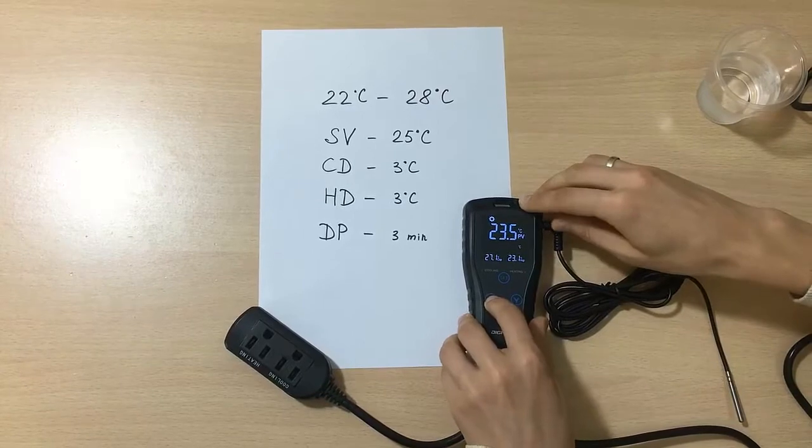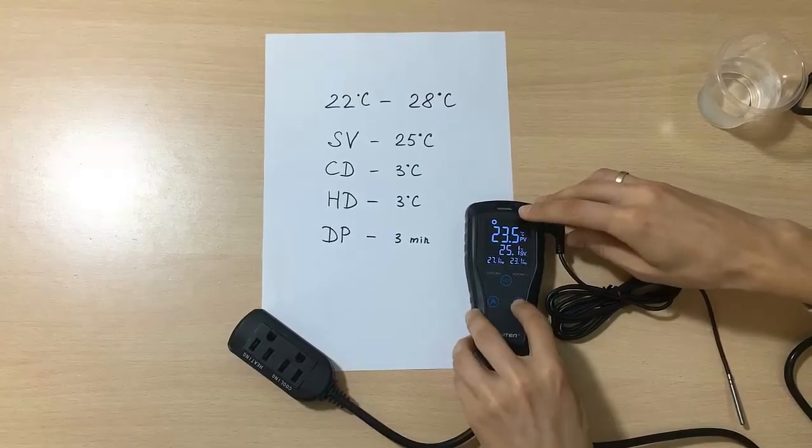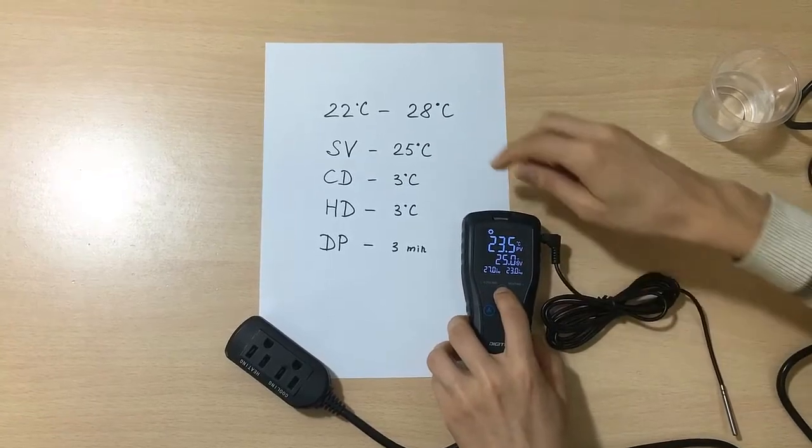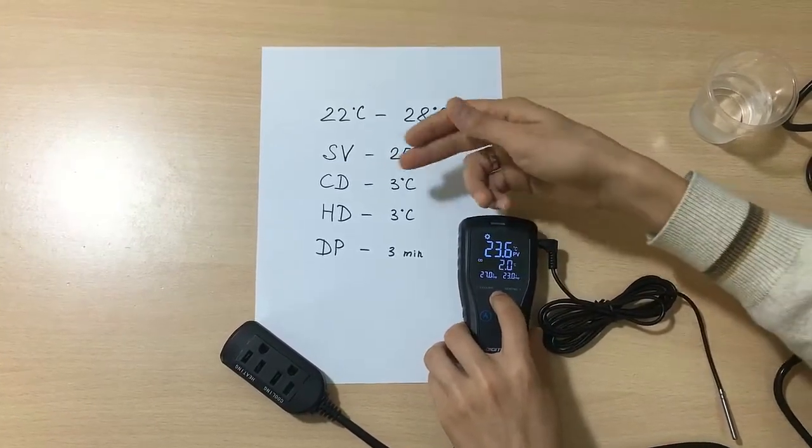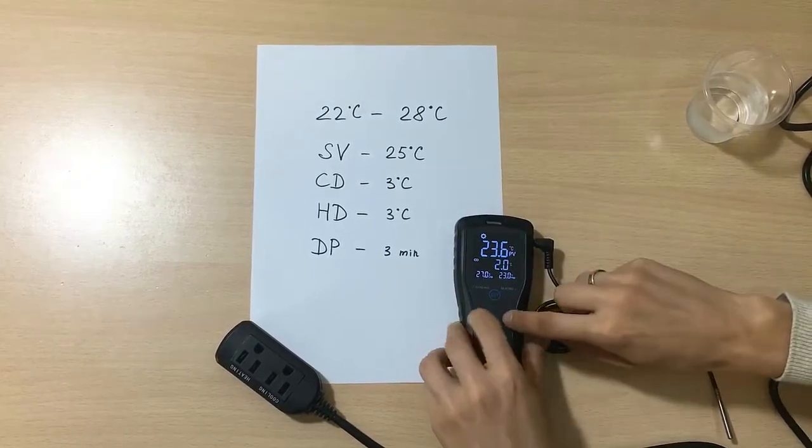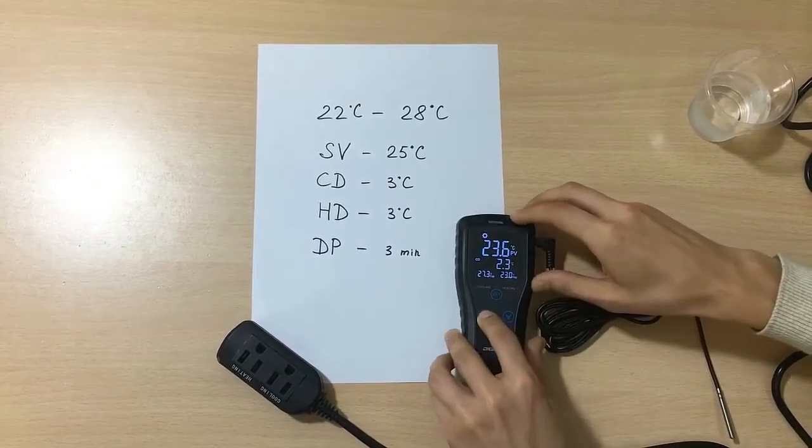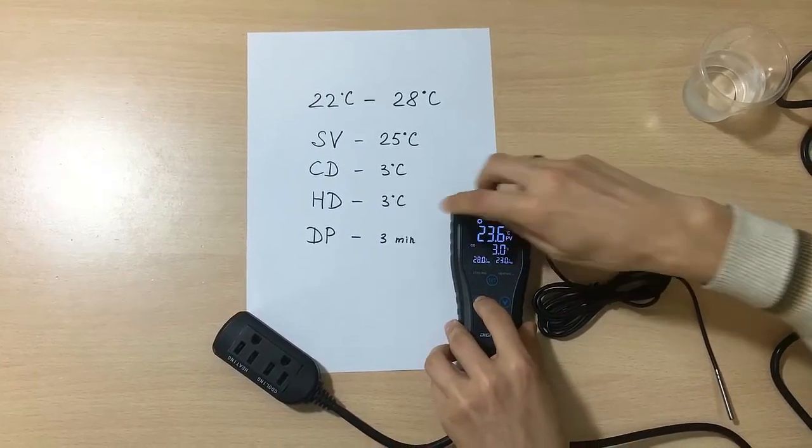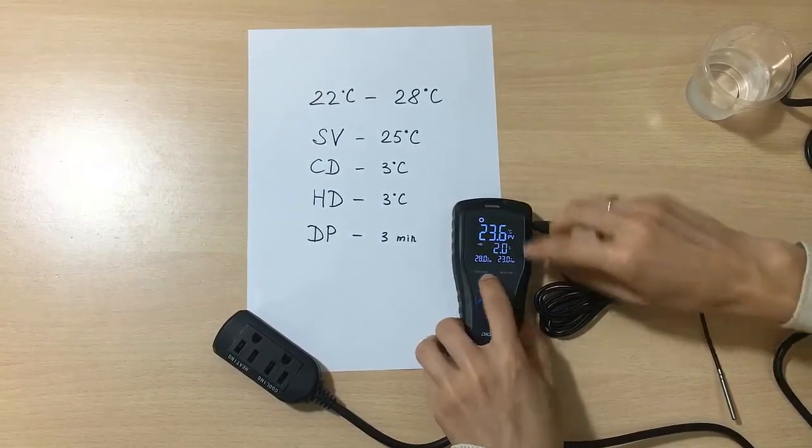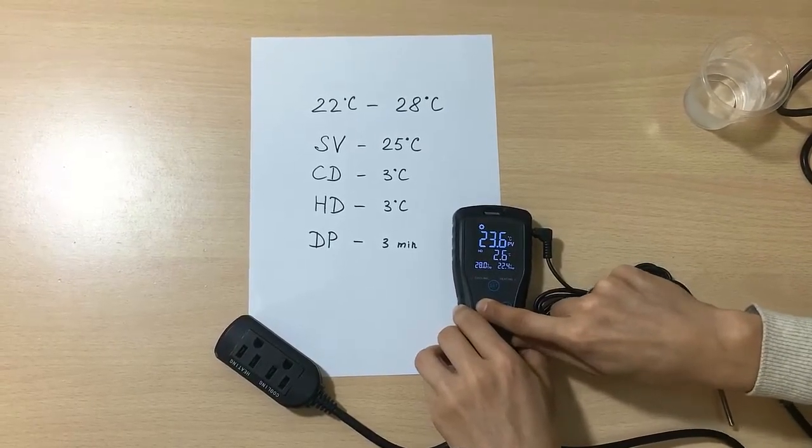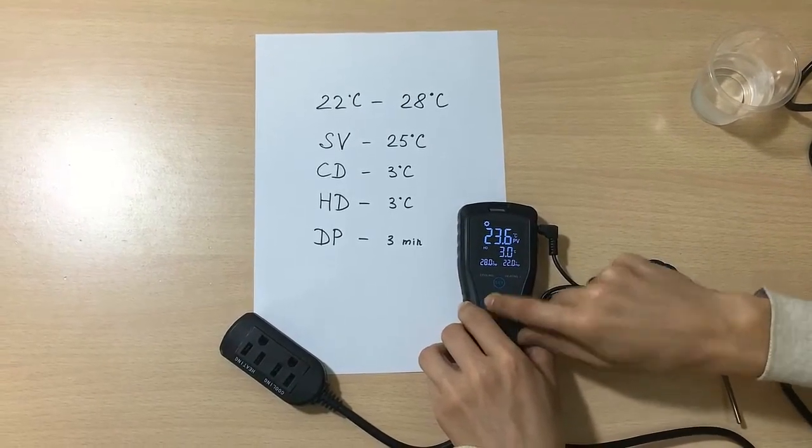We just do as we want and then we have to choose another one like CD, which is cooling differential. Now it's 2, but we have to change it to 3. So we just press the down button and we have 3 already. The next one is HD, which is heating differential. The same situation is applied with it. We just change the numbers to 3.